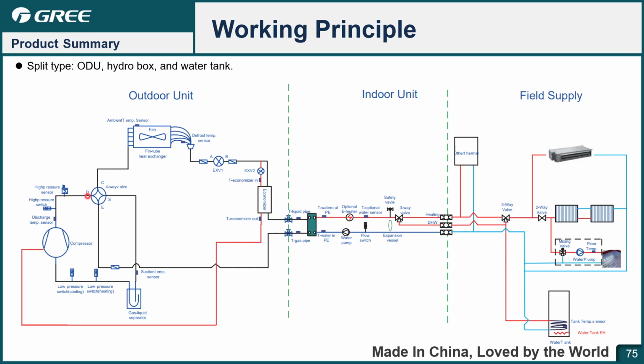for example, in heating mode, the hot gas will flow to the heat exchanger and exchange heat with the water, and then flow to here. There is an expansion valve controlling the throttling and flow mass, and then it flows to the other units. There is a defrosting temperature sensor, the fan, the fin tube heat exchanger and the ambient temperature sensor, and then it flows back to the four-way valve and to the gas liquid separator. There are two low pressure switches for different working conditions. One is for cooling, one is for heating, and it flows back to the equalizer.